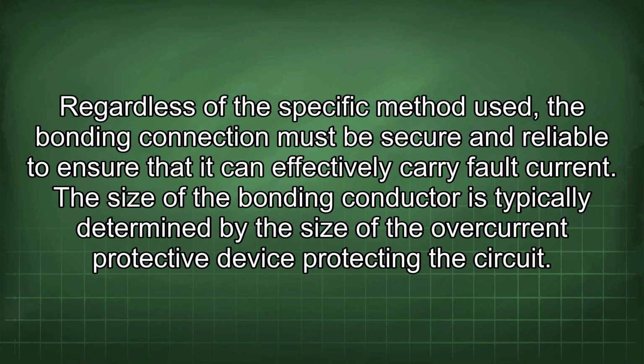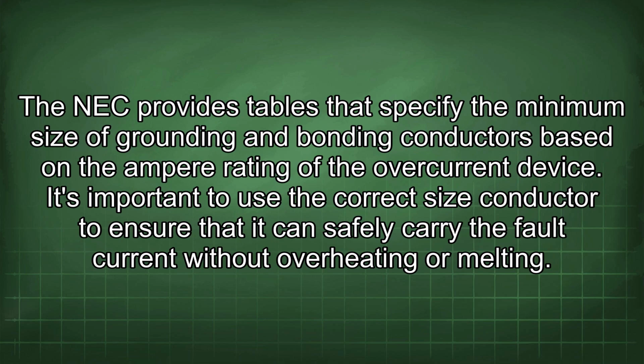The size of the bonding conductor is typically determined by the size of the overcurrent protective device protecting the circuit. The NEC provides tables that specify the minimum size of grounding and bonding conductors based on the ampere rating of the overcurrent device. It's important to use the correct size conductor to ensure that it can safely carry the fault current without overheating or melting.